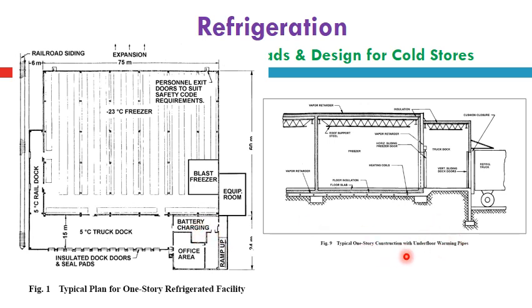This is a typical sectional view of underfloor warming pipes to keep the heat amount here, to add heat if needed for warming from the soil, if freezing from the soil, or in both directions. We can prevent the heat load from being transmitted from this floor of the refrigerated space to the soil, or from the soil to the refrigerated space, using these warming pipes. In addition, any frost forming on both sides can be removed by actuating it in defrosting time.